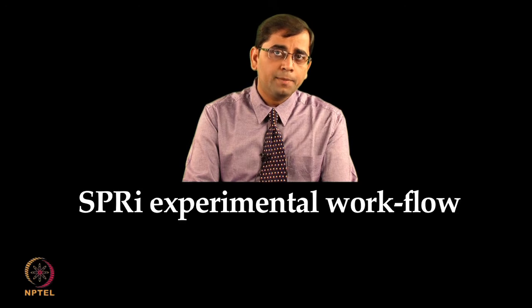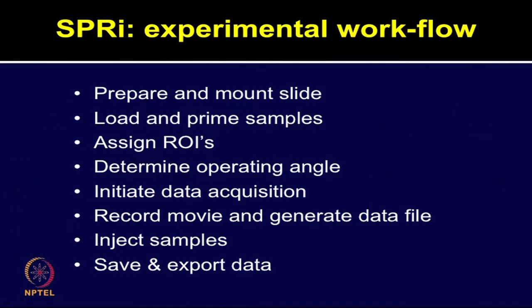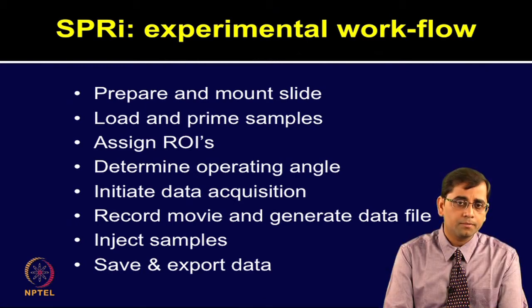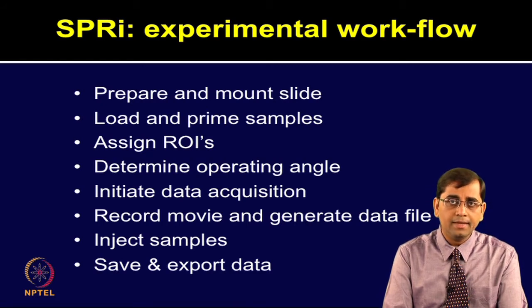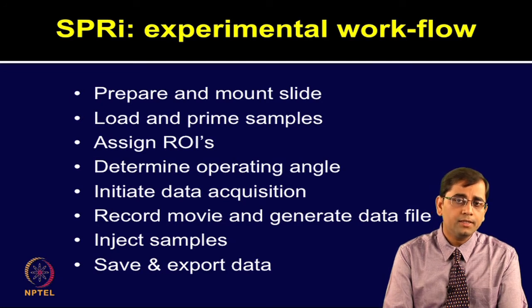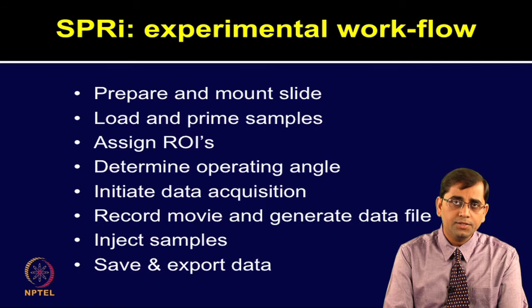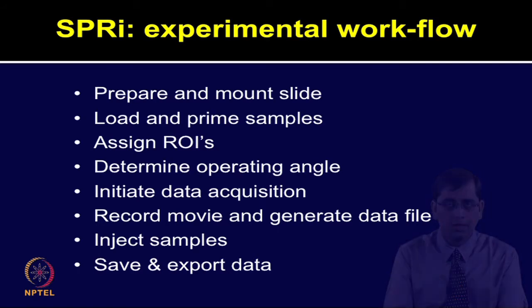Let us now talk about the experimental workflow involved in performing an SPRi experiment. SPRi fixes on a single incidence angle and monitors the reflection intensity for the whole array as a function of time. The various steps involved are: first, preparation of samples and mounting of slides on the prism; second, loading and priming of the samples; third, assigning regions of interest or ROIs; fourth, determining the operating angle; fifth, initiating data acquisition; sixth, recording the movie and generating the data file; then injecting samples; and finally, saving and exporting the data.